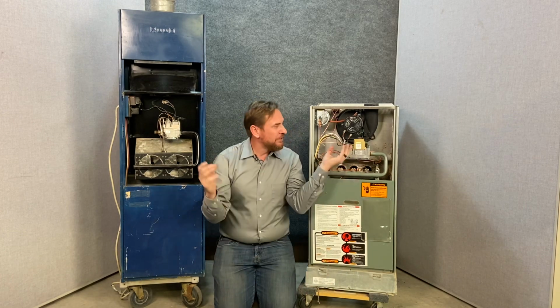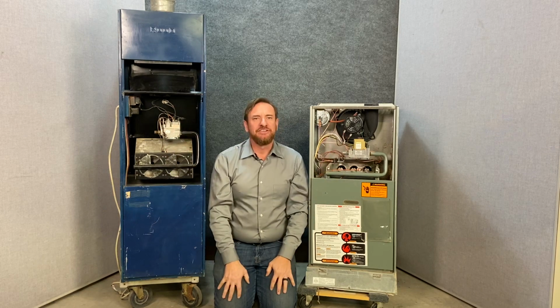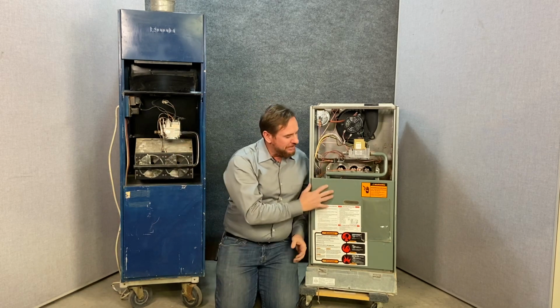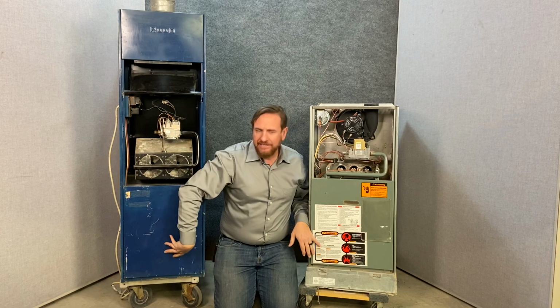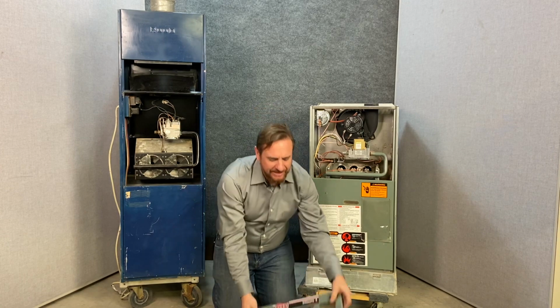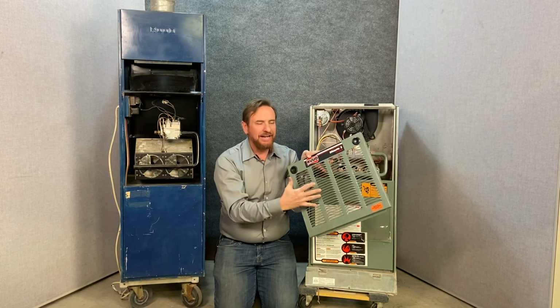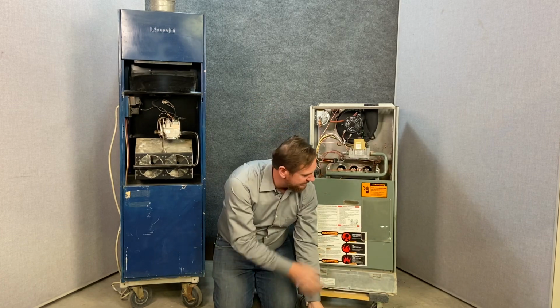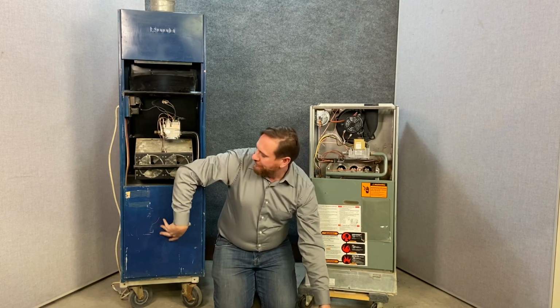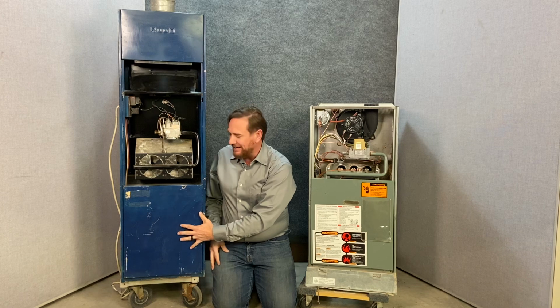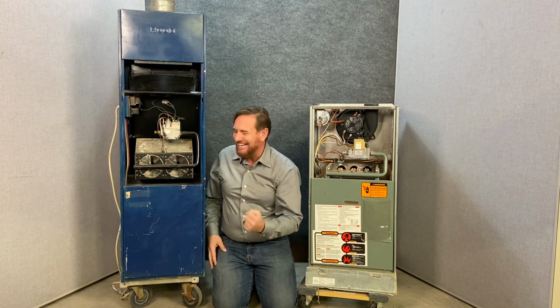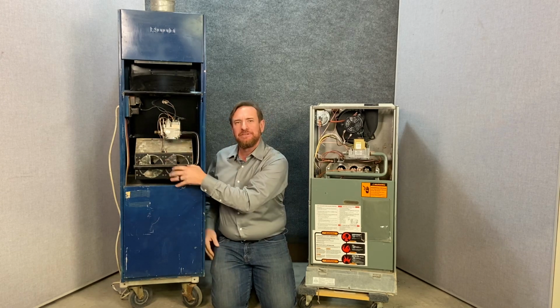So now we can get to all of our gas components, our gas valves, our burners. But next thing we have down here below is the blower doors. And if we notice, these doors are louvered. They allow air to go in. But where the blower is, it's a solid door. That's very important, because when this blower is running, it's pulling air from the house. And again, I can't stress this enough, it's not mixing it with the combustion air.